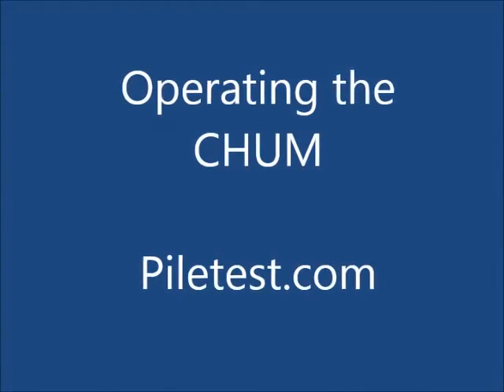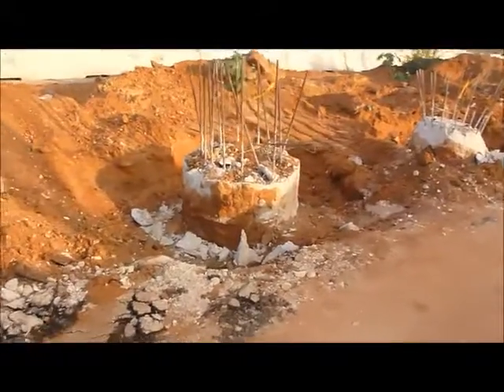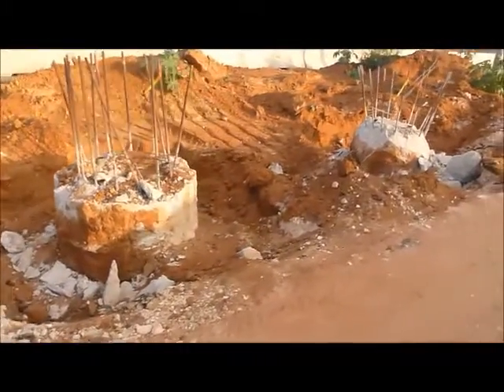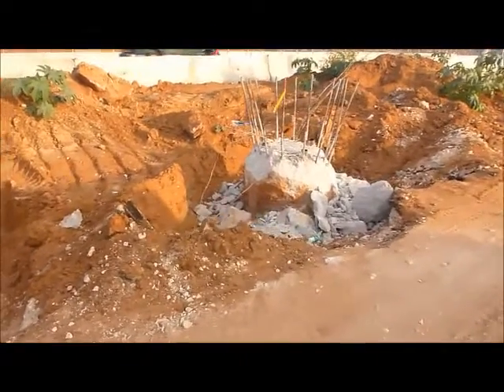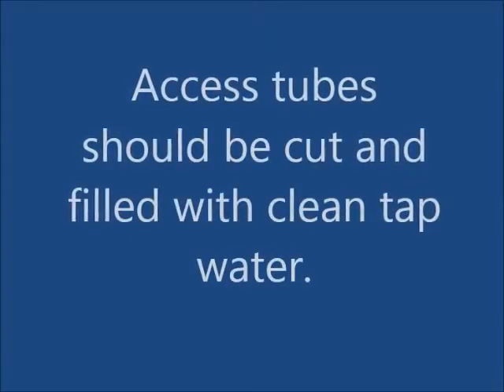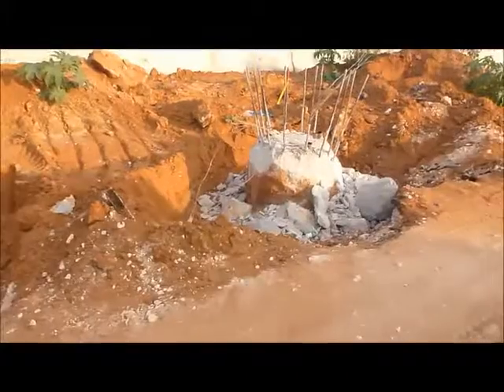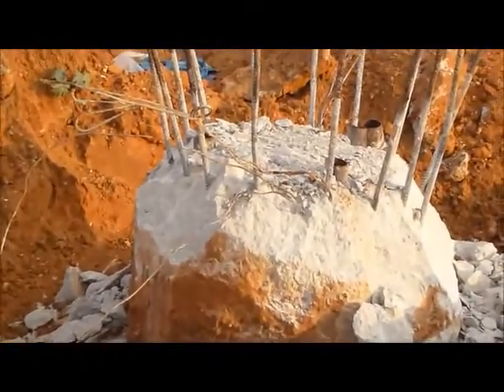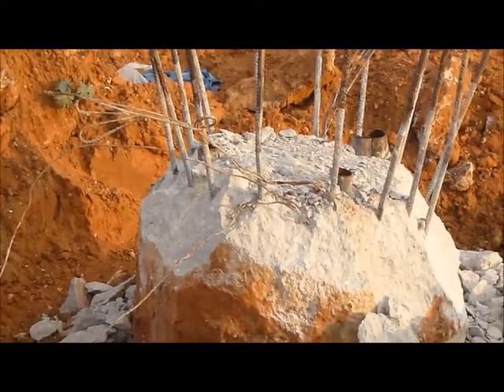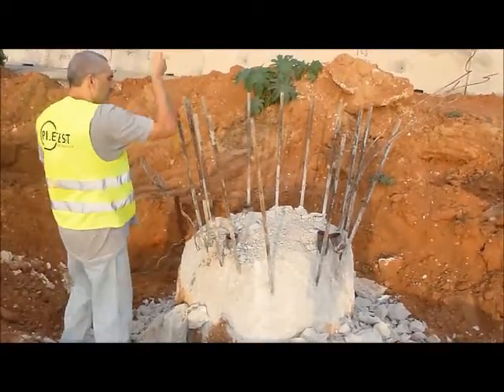Operating the CHUM cross-hole ultrasonic monitor. Access tubes should be cut and filled with clean water. It is highly recommended to test the tubes with a dummy prior to using real transducers.